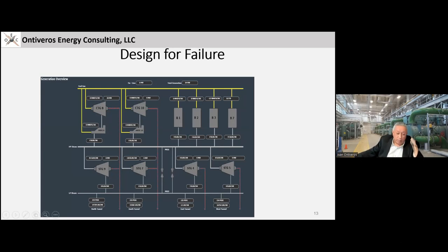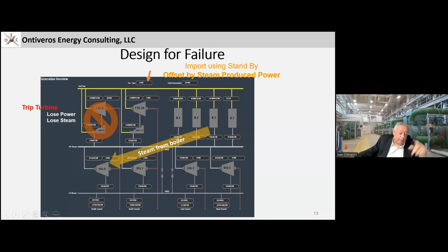One of the things I think is important when you're developing a system, and something we rolled into our thinking, was design for failure. What I mean by that is something's going to happen. A turbine trips and I lose the power, but I also lose the steam. The advantage I have is I can import power because I have a 25 megawatt standby agreement. So I can cover the power side of the turbine, but I can't cover the steam side of the system. So the boilers can still keep the steam flowing to the steam turbine, so I can keep part of my generation running.